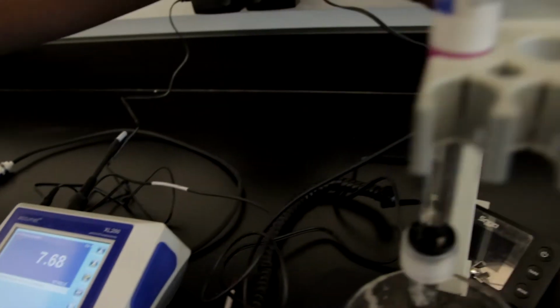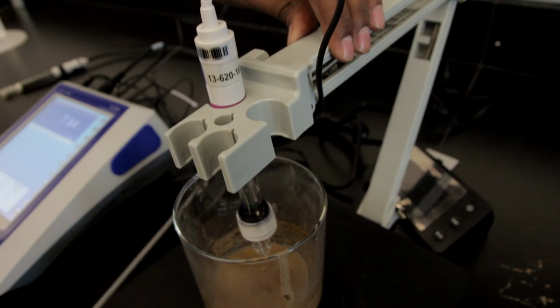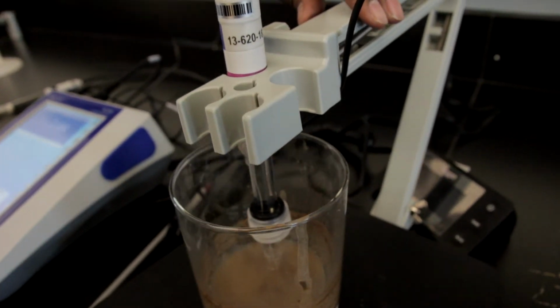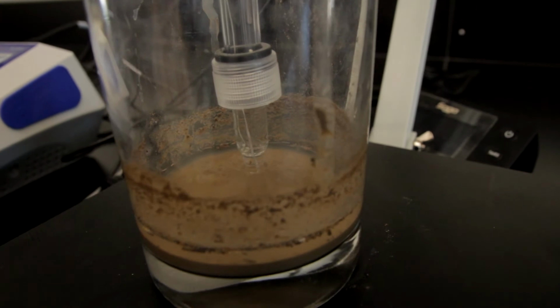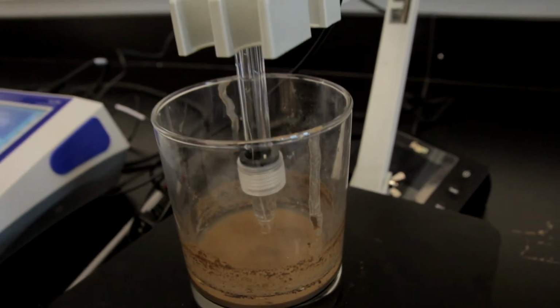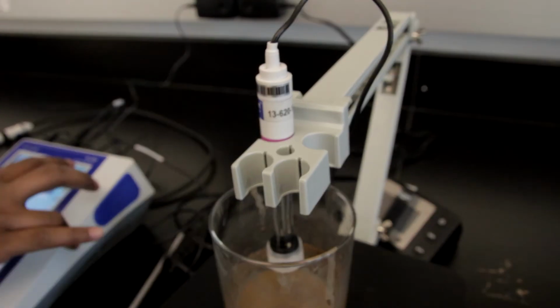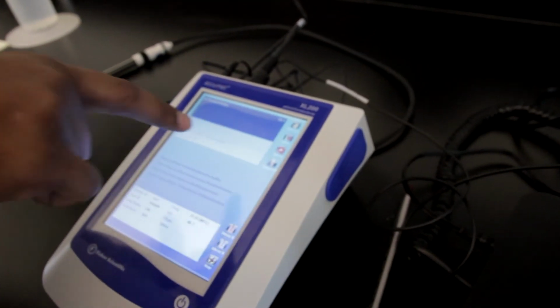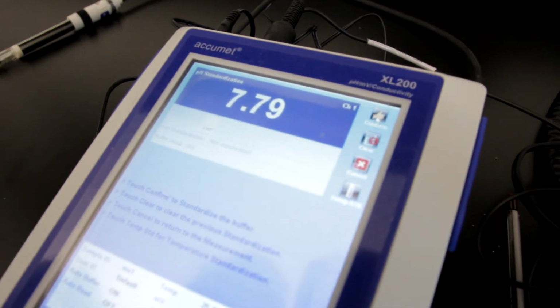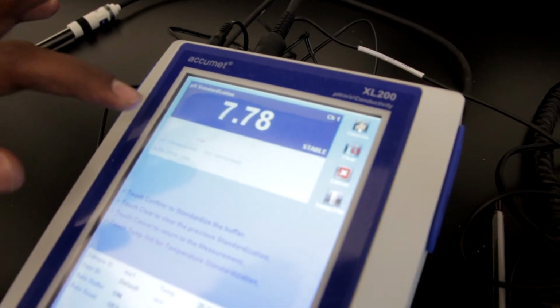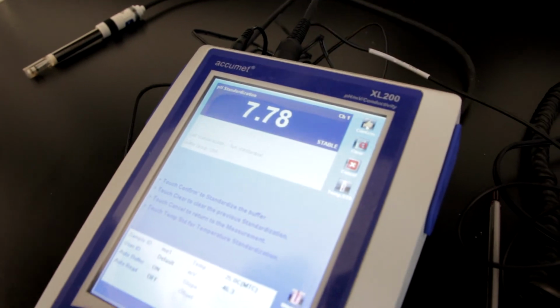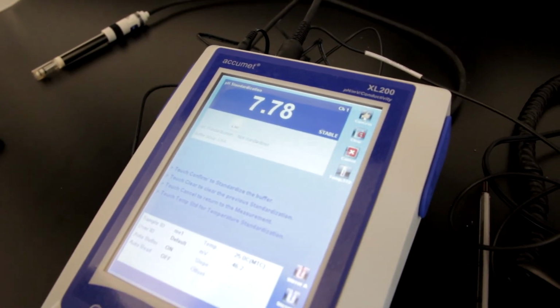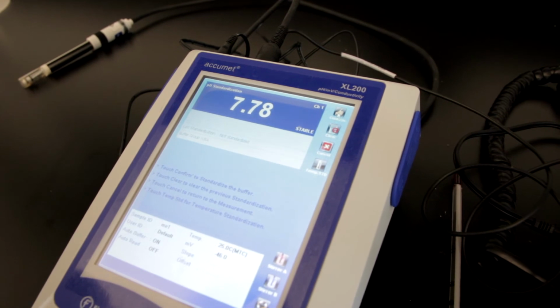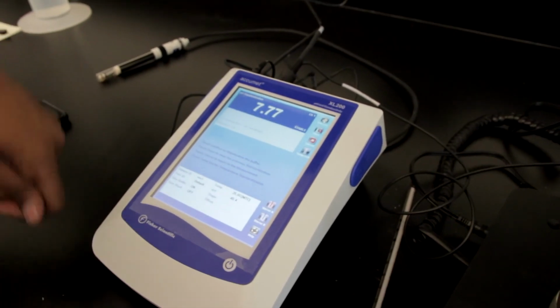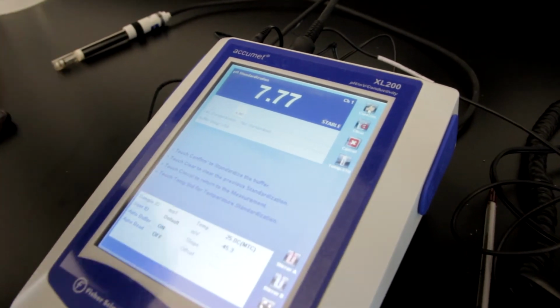The next step for us is to immerse the probe just over the slurry solution and not into the sand itself, just slightly touching the water. Now in the calibration setup, we go to standardize, and we check which pH value it shows. Once it says 6.997, we let it rest for 20 to 30 seconds so that we know what the stable pH value is. As you can see, the value is stable at 7.77 after almost 20 seconds. So you hit confirm here.